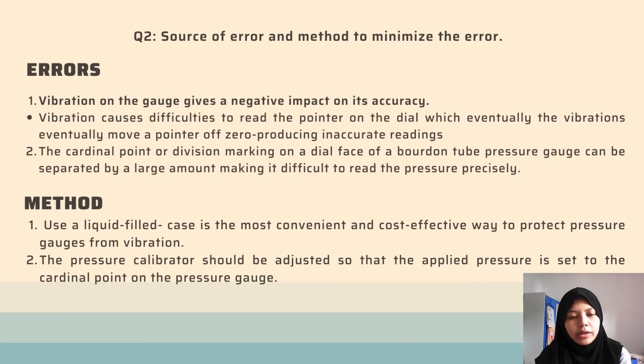The second error is that the cardinal points or division markings on the dial face of a Bourdon tube pressure gauge can be separated by a large amount, making it difficult to read the pressure precisely. The method to minimize this error is that the pressure calibrator should be adjusted so that the applied pressure is set to the cardinal point on the pressure gauge.